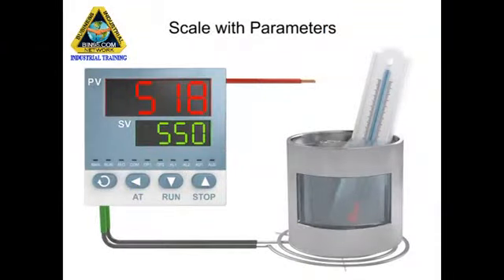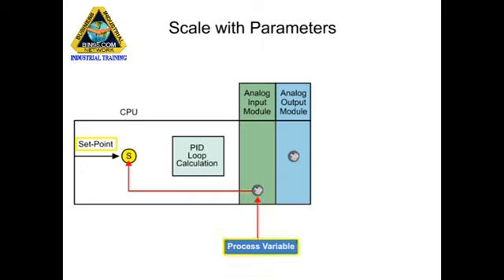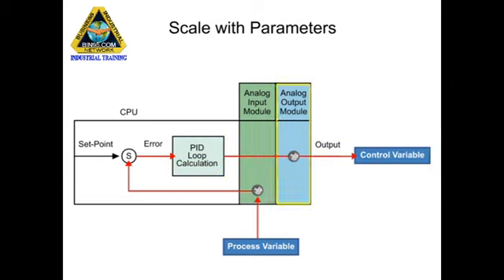PID control is a common closed loop system used to maintain physical properties such as pressure and temperature in automated processes. The PID instruction controls the closed loop by comparing the input or process variable from an analog input module to the system setpoint. The difference between the setpoint and the process variable is referred to as error. The error is analyzed by the PID loop calculation and provides an output or control variable to an analog output module to meet the setpoint defined by the system requirements.